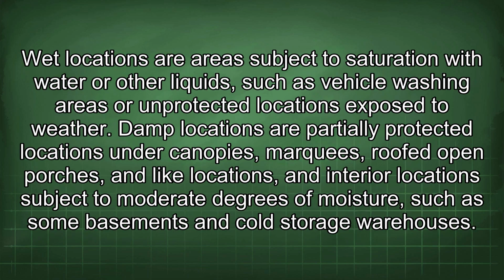Wet locations are areas subject to saturation with water or other liquids, such as vehicle washing areas or unprotected locations exposed to weather. Damp locations are partially protected locations under canopies, marquees, roofed open porches, and like locations, and interior locations subject to moderate degrees of moisture, such as some basements and cold storage warehouses.